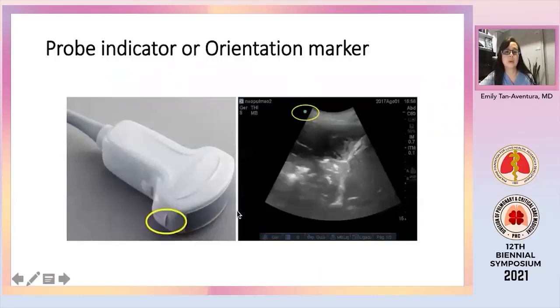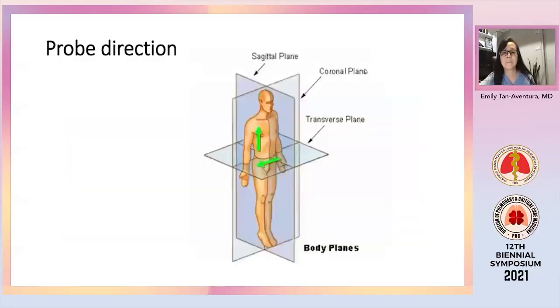On the transducer probe, you will see an indicator or orientation marker. This corresponds to the blue dot, or sometimes the green dot, on the screen. This just helps you orient yourself to where your probe is on the patient and what you see on the screen. For orientation purposes and for uniformity, the indicator should be directed cephalad and to the right of the patient. This way, everyone will know the orientation of the image on the screen.